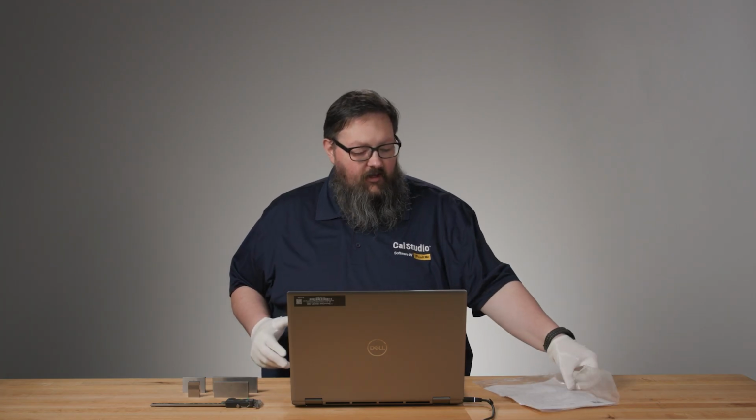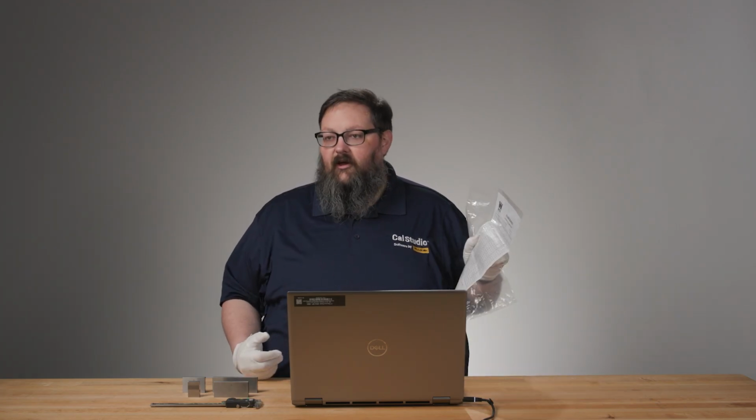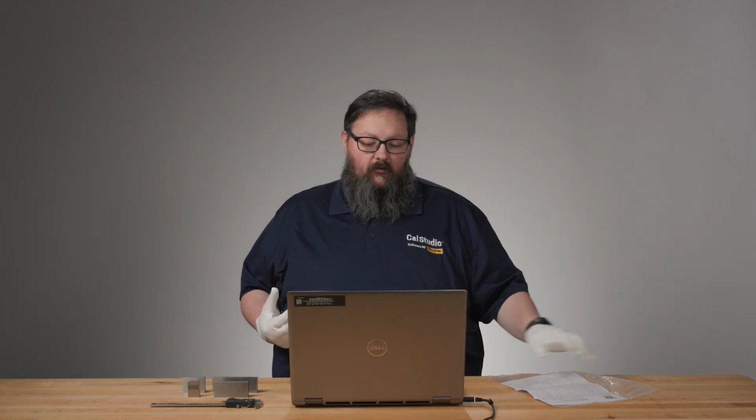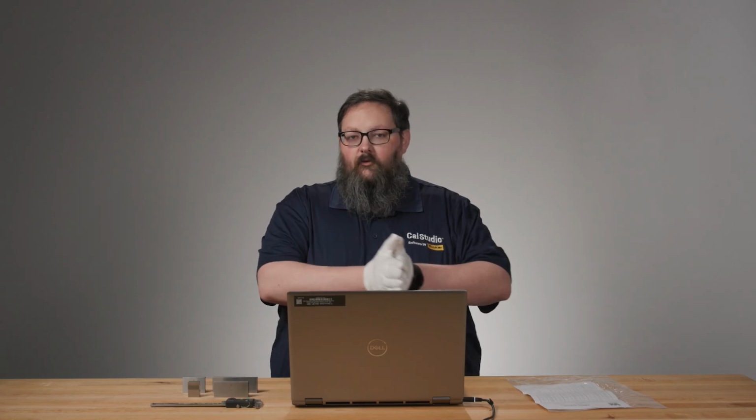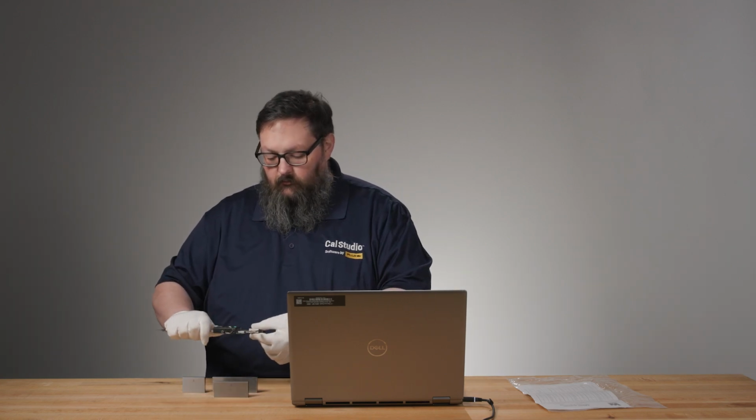And I also have for my gauge block set the gauge record that tells me what the deviation for any given block is. The resolution of this instrument isn't sufficient to show that in any of the applied values, but we could alter the applied value here to account for that in what the tolerances are and what the test limits are as we move forward.